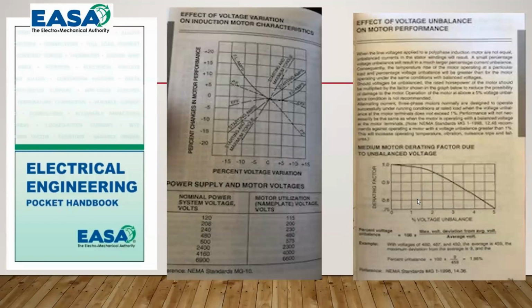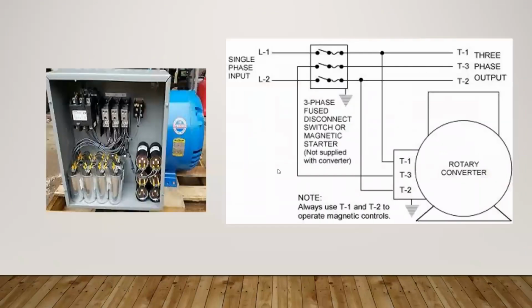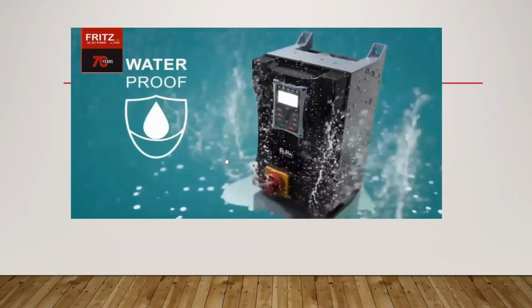And so you should be derating the three-phase motors that you're using on those. If it's off even 5%, you're supposed to derate it 25%. But there's a lot of motors out there, and people keep wondering, well, why do they not last as long? Why do they burn up? Why do they have problems? A lot of it has to do with the motor design itself, or the phase converter design just is not giving true balanced three-phase power. And then that also affects the efficiency level.